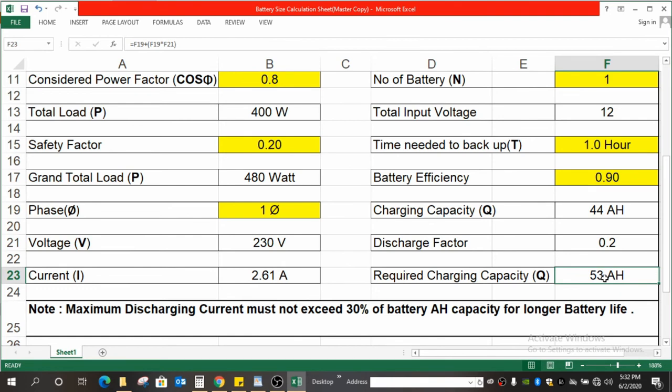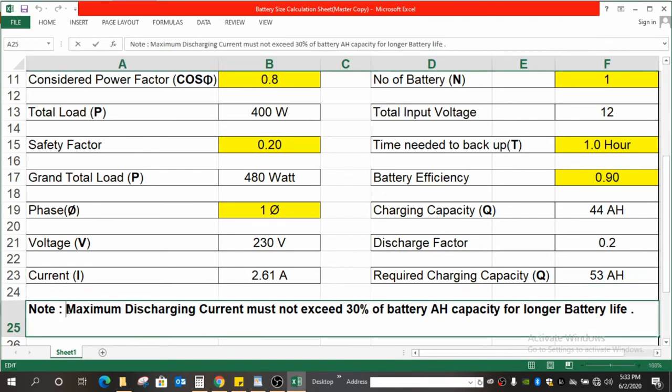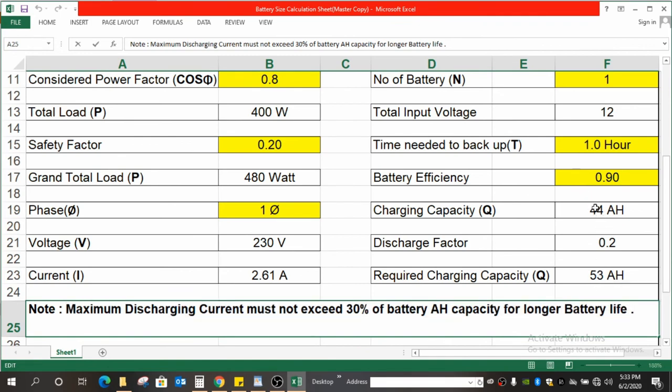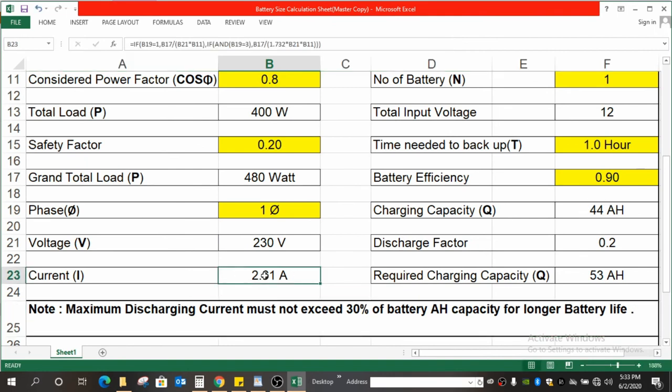While selecting, two things need to be noticed. One is the charging current and the second is discharging current. What is the discharging current? I have written over here for your notice: maximum discharging current must not exceed 30% of battery Ah capacity for longer battery life. That is, if the capacity is 44 Ah over here, 30% is 13 to 14 A. In no case should the discharge current of the battery be more than 14 A at a time. That is, the load current over here is the discharge current of the battery.